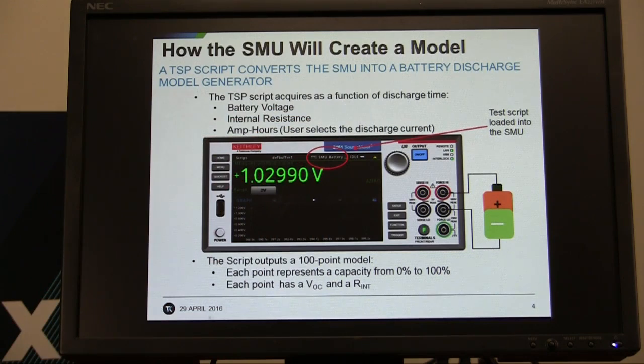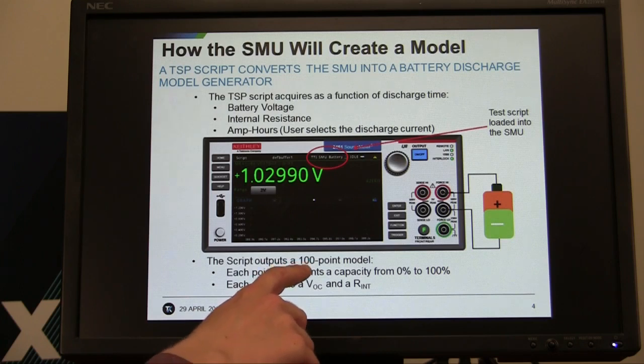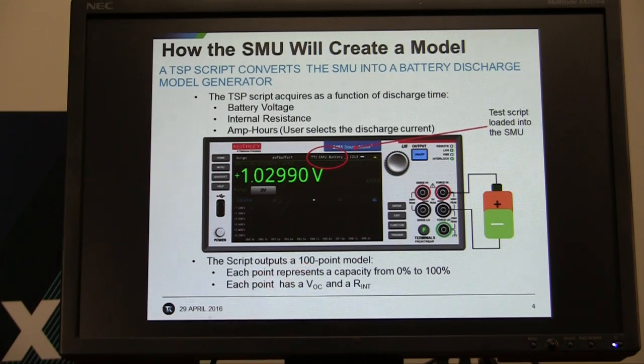When it's done discharging the battery, it's going to produce a 100-point model that can then be loaded back into the 2281S battery simulator to be used to simulate a battery.